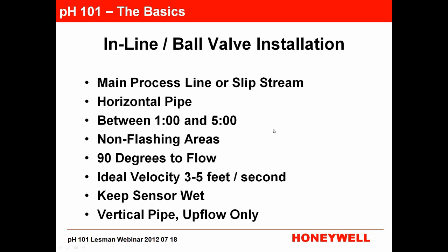A smart place is not necessarily an easy-to-get-to place. You want to get the sensor somewhere it's going to stay clean and see real, live process data all the time — not in a dead zone with slow flow where it gets fouled. The ideal installation is in a main process line or in a slipstream with good flow. It's best if that line is horizontal — you want to stay in a horizontal line rather than a vertical line if at all possible.